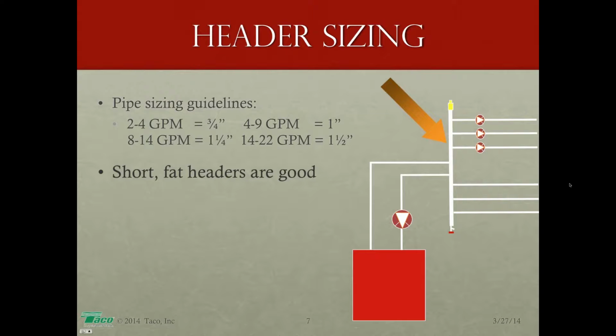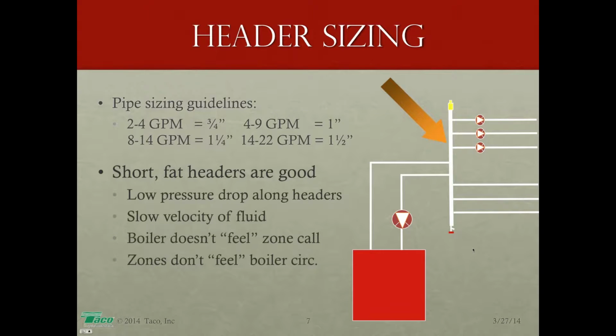Now we'll pump away from the point of no pressure change on the header as we should, but on the boiler, that's the way it really should be done, because it's not a pumping away issue, it is a keeping the pressure up issue. Alrighty, short fat headers are good. We like short fat headers. The reason we like short fat headers is not because I'm a short fat guy, it's because we like short fat headers. Short fat headers help us with hydraulic separation.